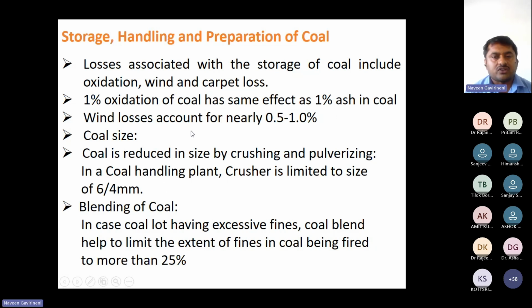And there is windage loss, as you know, coal is dumped in the atmosphere only. Fines will go with the wind, so we have considered 0.5 to 1% here. Then there is coal size, as I have already explained: 6 mm coal size for the CFBC boiler and AFBC. That terminology I will explain when coming to the boiler point of view.